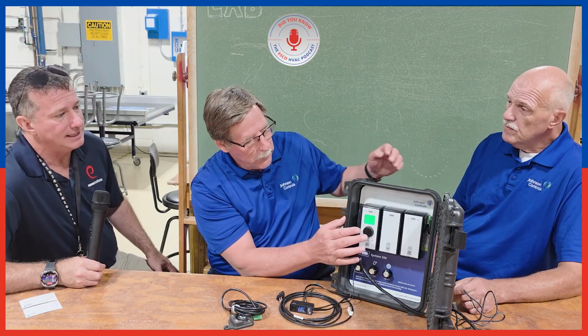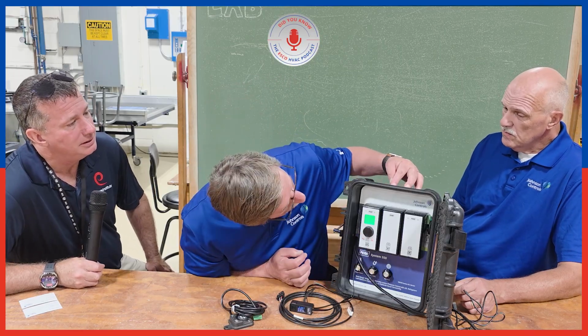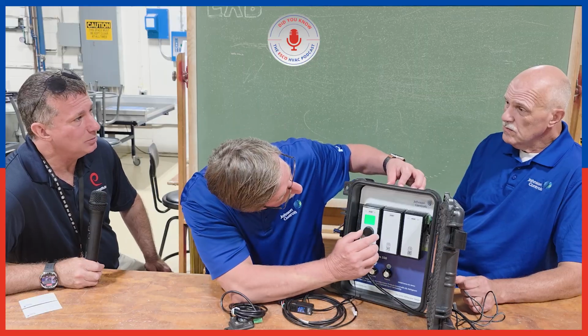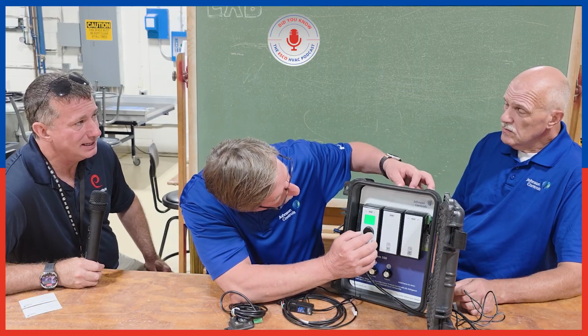Oh, now that's really adding some features to it. If we think about a system that has multiple sensors and we're tracking that LFL, and now we can actually track and graph, we can monitor. What if I have a sensor picking up a small amount of refrigerant leak at a particular time every day? Now I can go back and look at my trends and go, oh, that's when we went into hot gas defrost. I better start looking for a leak on that loop. Sure. Yeah, that is a very good point.